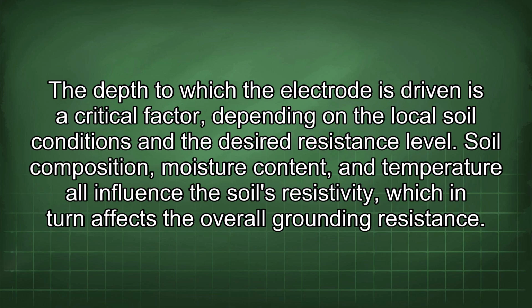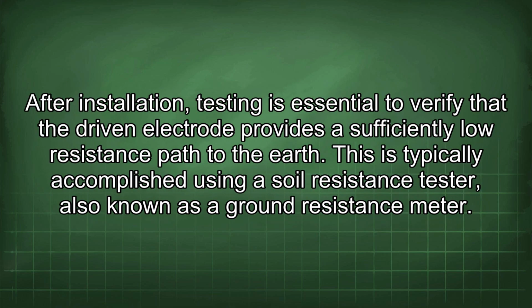The depth to which the electrode is driven is a critical factor, depending on the local soil conditions and the desired resistance level. Soil composition, moisture content, and temperature all influence the soil's resistivity, which in turn affects the overall grounding resistance. After installation, testing is essential to verify that the driven electrode provides a sufficiently low resistance path to the earth. This is typically accomplished using a soil resistance tester, also known as a ground resistance meter.